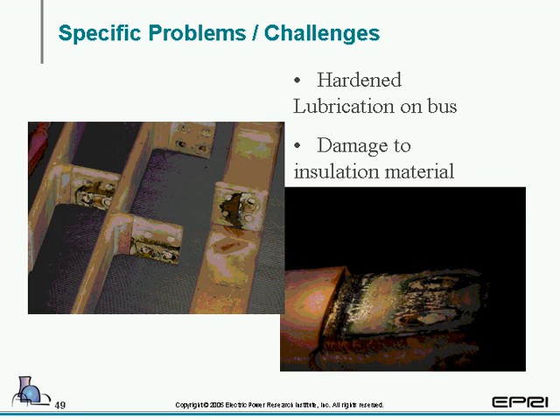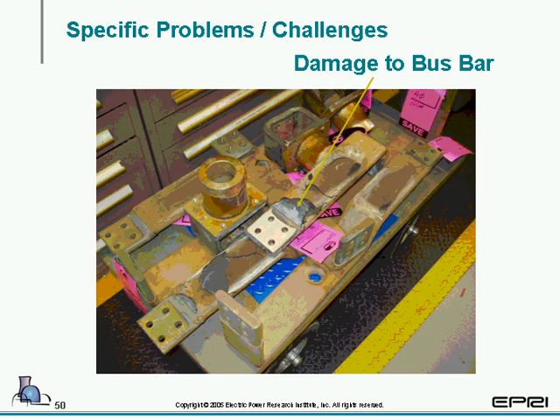And when we pulled apart the actual bus, we found hardened lubrication on the bus and damage to the insulation material. Now, when you get to this step, by taking apart the bus, as you'll see in this particular slide, if you start to look at your bus and disassemble it, it's a good idea to expect the worst. Because as you take it apart, many times I've found that you create problems.